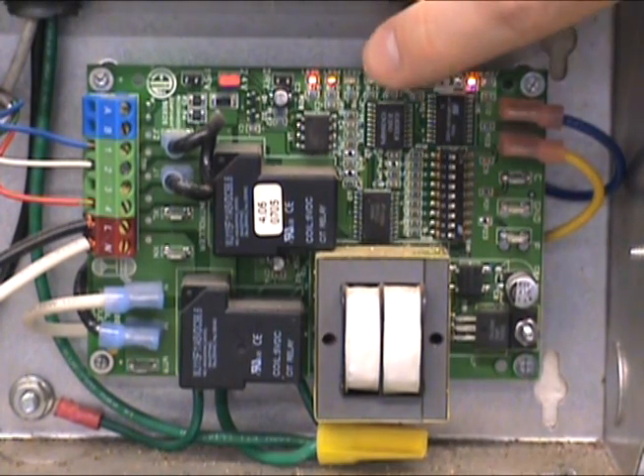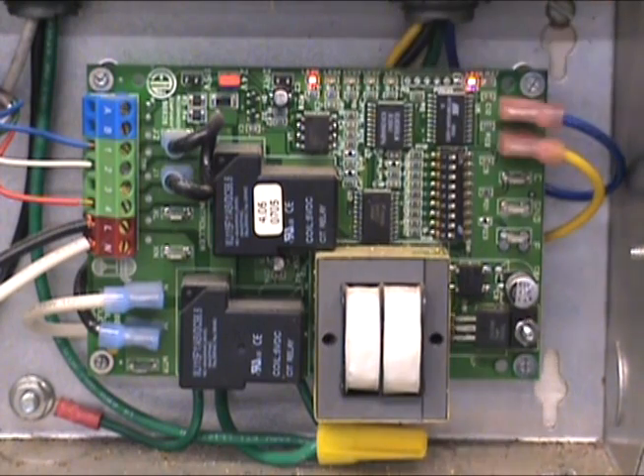Once the dip switches are on, if a fault code is present, LED4 will be flashing. Count the number of flashes in sequence between the pause. This number of flashes is the fault code.